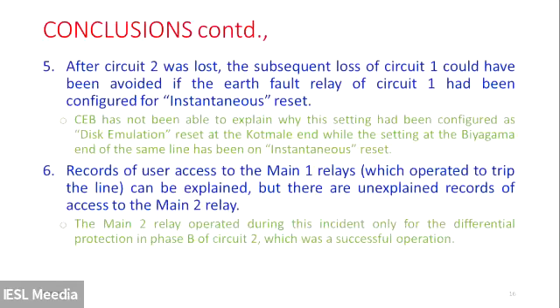one other thing that we could observe is that once the circuit 2 is gone, what is remaining is circuit 1, and our load flow studies also showed that if we had the circuit 1 in the healthy condition, we could survive the system without collapse. And when we went through the details of the relay settings, etc., we found that because this is somewhat unusual, it operated after 22.33 seconds from the initial high impedance earth fault, or whatever the earth fault on the circuit 2.